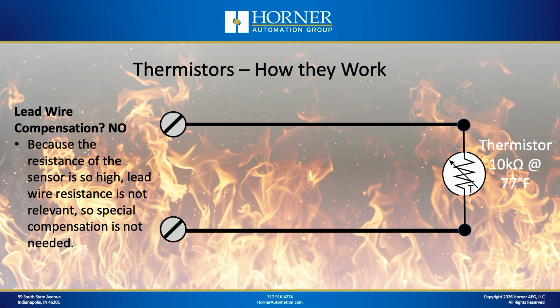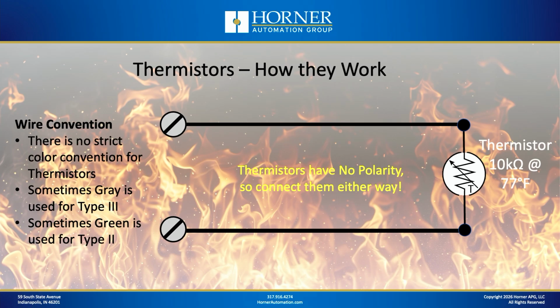All right, now, do you need to deal with lead wire compensation with thermistors like you do with RTDs? Absolutely not. The wire resistance of the leads running out to the thermistor is basically just a round-off error. I mean, literally. So you don't need to worry about that. There's nothing special to deal with thermistors when it comes to lead wire compensation. And typically, you don't have any color convention that's all that standard with thermistors either. And they don't have a polarity. So you don't need to worry about which side you connect to plus and which side you connect to minus.